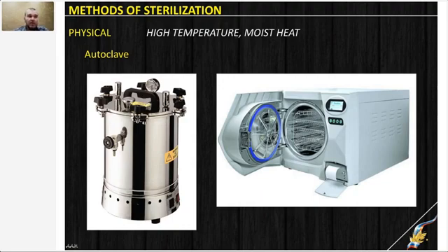So the autoclave has several regimens of work, and it can work as a boiler when simple heating of water up to 100 degrees Celsius occurs. And usually the autoclave in no-pressure regimen is used to sterilize different types of culture medium. And of course, the main benefit of the autoclave is that it can be closed, it's made of very thick metal, and it can raise pressure significantly.